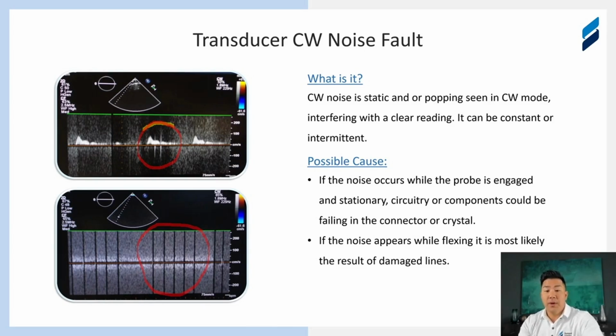And so the idea here is that if you're flexing that strain relief area of the cable of the probe and you can induce the noise, for sure it's the probe, but you've got some wire issues that are either chafing together and shorting together when you're flexing, or there's a microfracture on the coax line and it's just stretching and coming back together and causing that noise. If you can't induce it, but it's the probe, then it's likely an intermittent connection in the crystal or the connector itself in the probe.